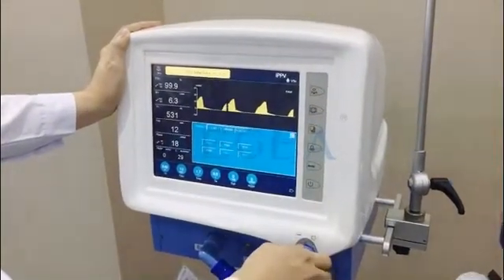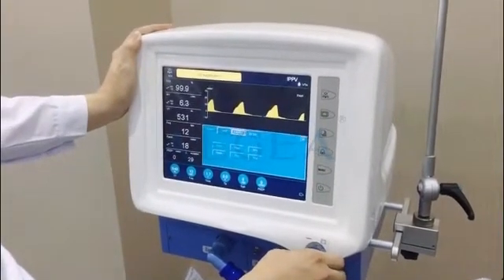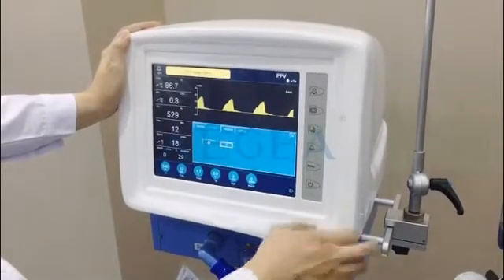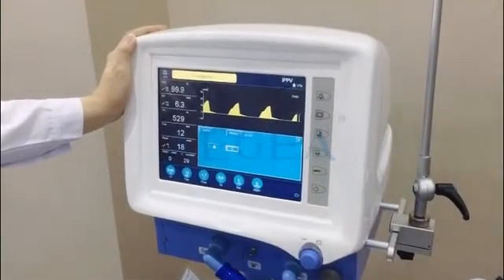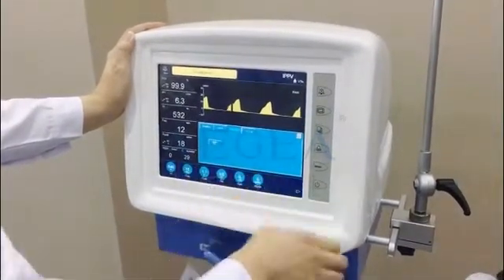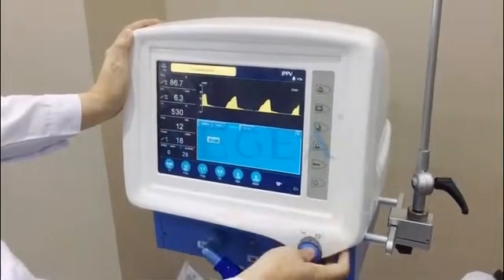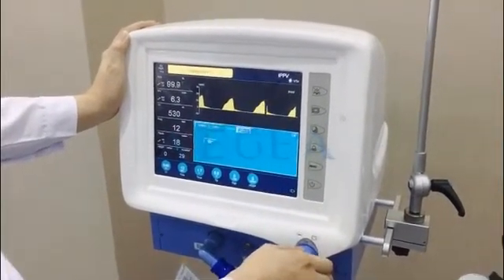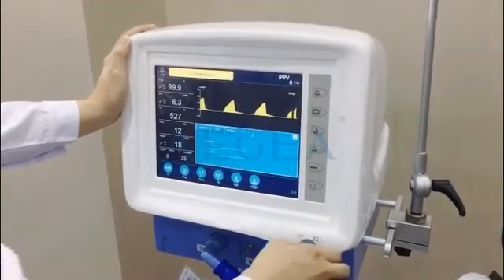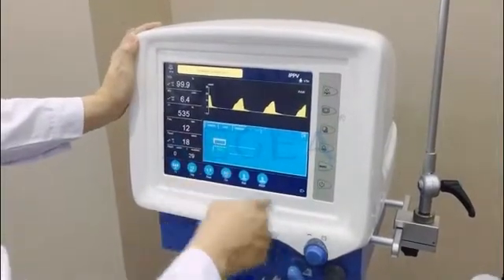The gray key is the lock. We can lock the monitor to prevent patients from touching it by accident. And nebulizer — we can turn the nebulizer here using this icon. We can also adjust the ratio of oxygen, for example 21%.